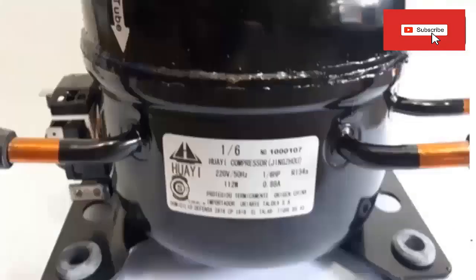9. It must be charged from the liquid phase to ensure accurate mix composition. 10. With a safety rating of A1, non-flammable. 11. Compressors can be loaded with most current oils, but better oil return will be obtained with polyester oils.